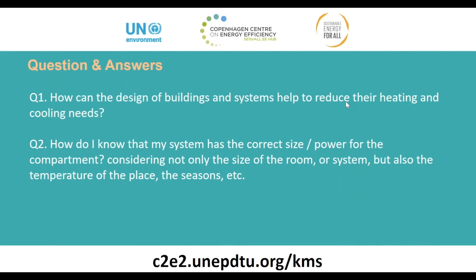For cooling and heating loads, if you cannot measure, then you can also theoretically calculate to estimate what your actual system capacities could be. You may have to take several factors into account though. That is like the solar radiation levels, your ambient conditions, the wet bulb, dry bulb temperature, humidity, the orientation of the building, how is it facing, is it east, west, north, south, the occupancy rates, how many people are staying in that particular compartment, room or a building, infiltration or leakage rates if there are any.